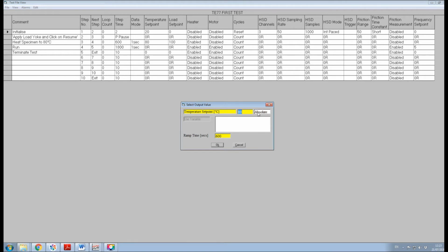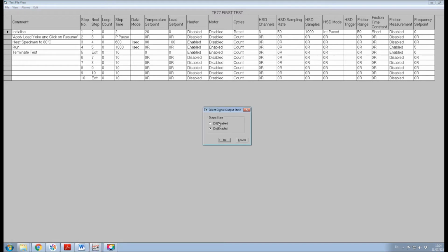At step 3, the temperature has been set to an absolute value of 80 centigrade and a ramp time of 600 seconds. This means that the temperature set point will be ramped from the preceding 20 degrees centigrade to 80 degrees centigrade in 600 seconds. In other words, 1 degree every 10 seconds. Using a sensible ramp time will ensure good control and minimize overshoot of the set point. It is, of course, important to enable the heaters for this step.